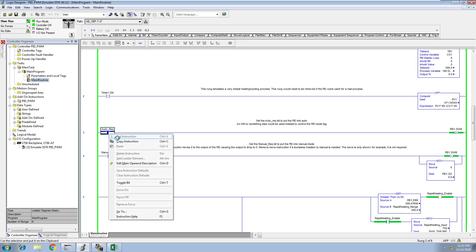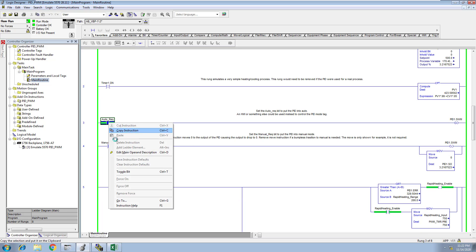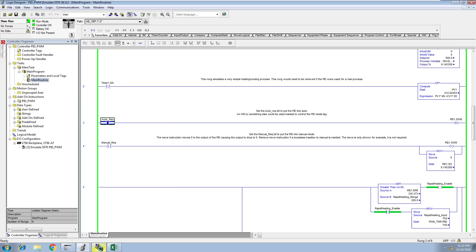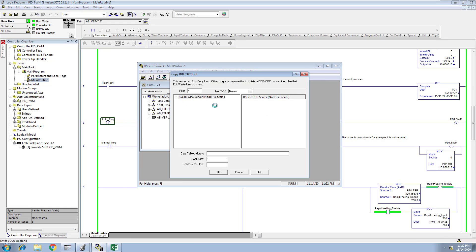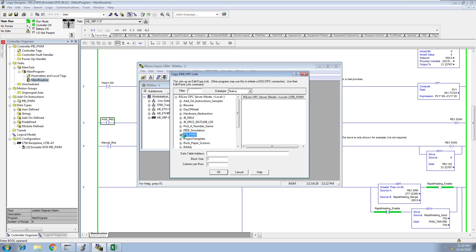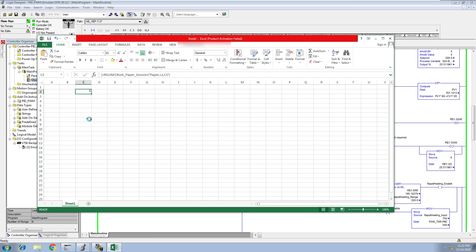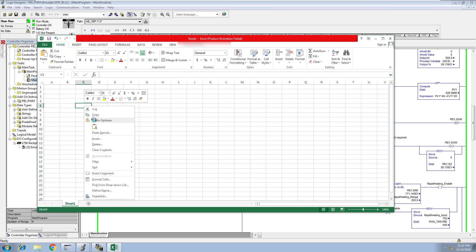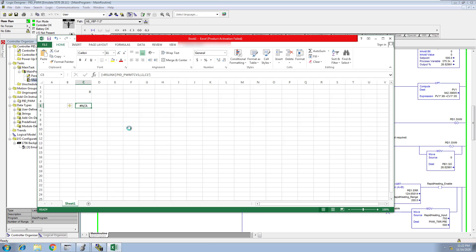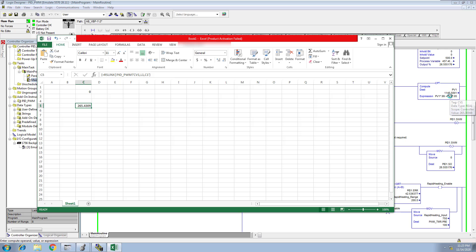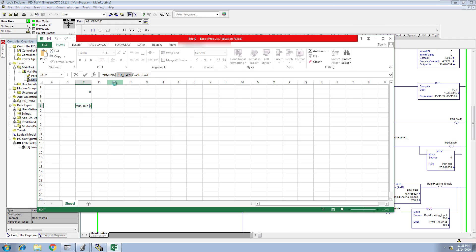Then we're going to come into our RSLinx, grab our DDE link again, come in here, and go to PWM. We're going to grab our CV, copy that, and paste it over here. So you can do multiple things. We're going to paste as link, and it will actually come in. This is the live data that's flowing through there right now, so this is the CV data right here. You can see the link that it posted. It equals RSLinx, and then this is the actual OPC topic, and then CV1 is the tag, and then L1.